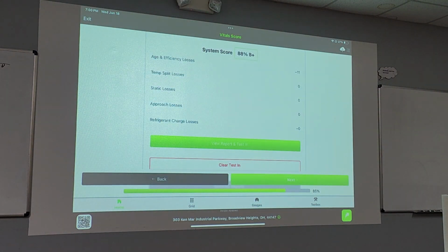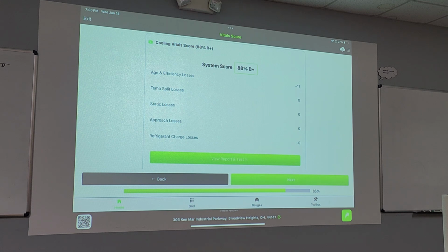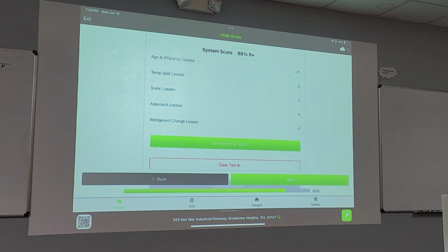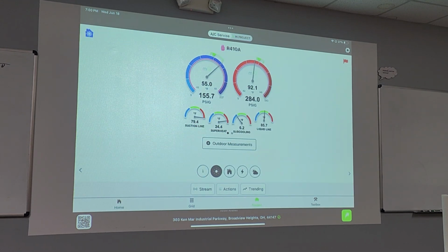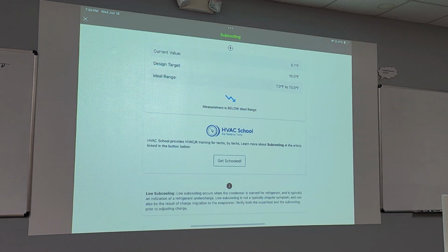Well, we were heavy to begin with years ago. Yeah, and then my pressure probe's Schrader depressor tip was sticking out a little further than I thought. Did we pull like 1.5 pounds out of that or something? No, we pulled out all the charge and it was like a half a pound too much. So this is why subcooling is low, right? Our tolerance for subcooling is plus or minus 3 degrees from target. So right now profile target is 10 degrees, we're at 6.1. So it is actually a little bit low on refrigerant, thanks to me.